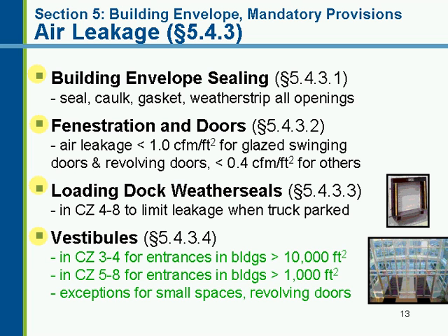Now, within the text itself, there's also been some revisions at the end of that. There had been some questions that had come up about, well, can you put heat in a vestibule? And if you wanted to do that, where do you draw the line between what's the building envelope versus what is inside or outside of that? So the language at the end of 5.4.3.4 says that the exterior envelope of conditioned vestibule shall comply with the requirements for a conditioned space.